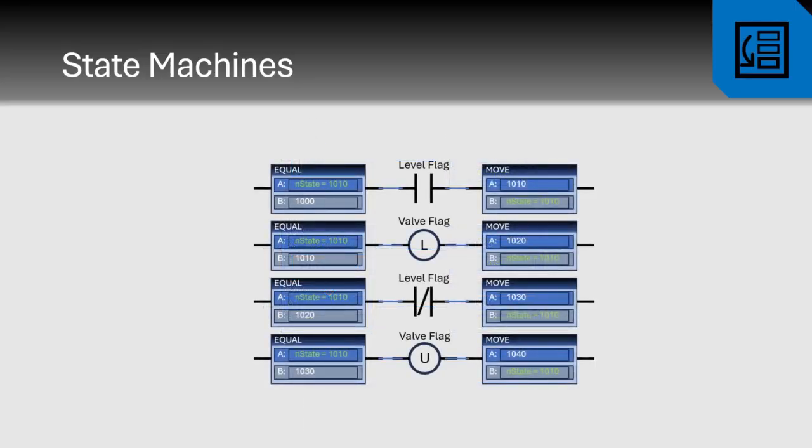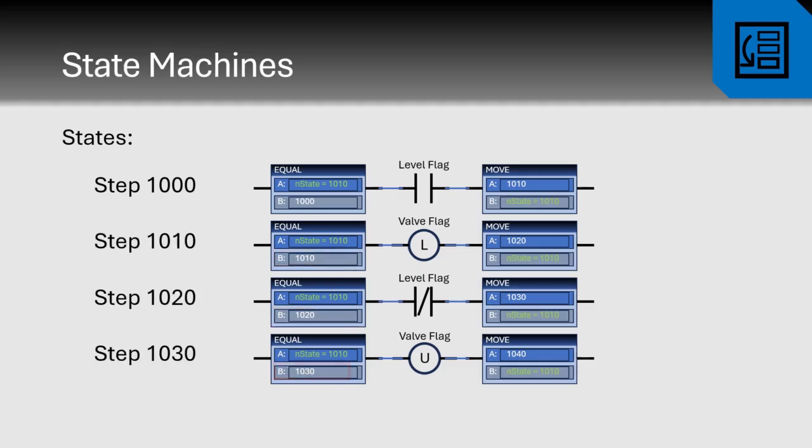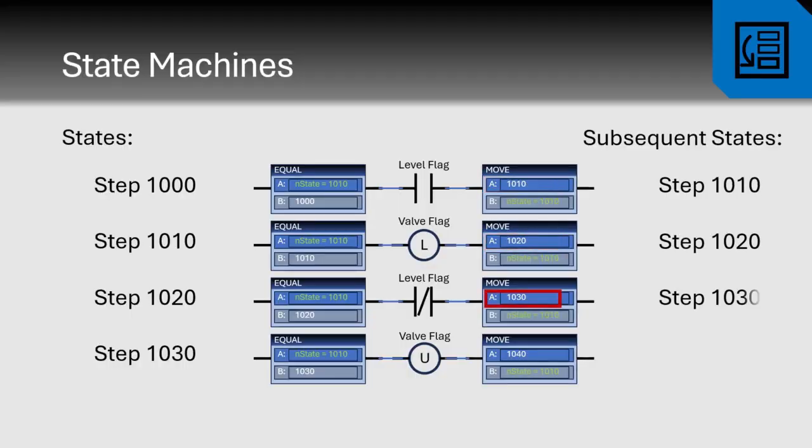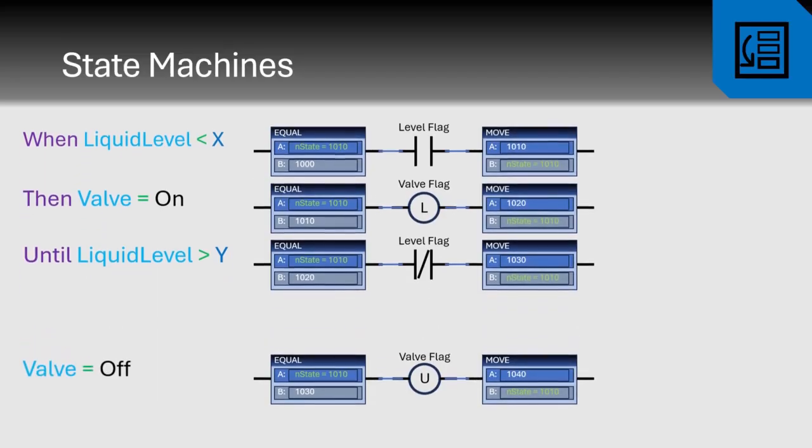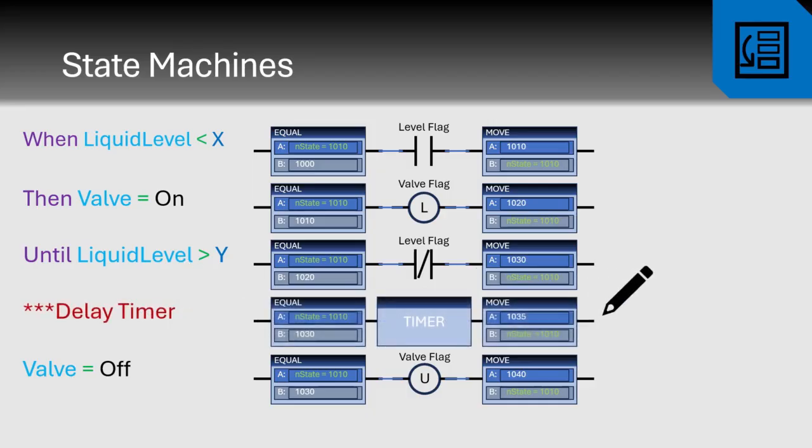State numbers are intentionally large. Each numerical place value provides an opportunity for elaborate methods of organization. For example, states in the 1000s range identify startup tasks, while the 3000s contain a shutdown sequence. The gaps between state numbers make revisions easy. When the sequence requires revision, simply add a state rung in the proper place in that sequence, likely between rungs. Only the state number above the inserted state must change.